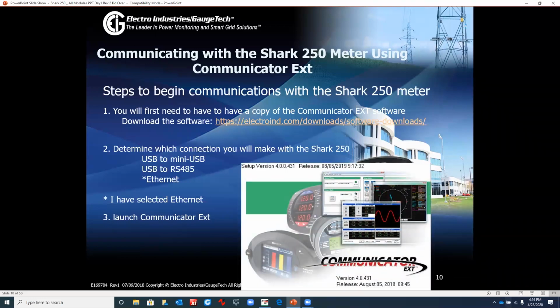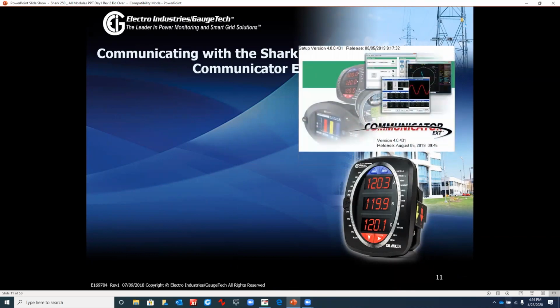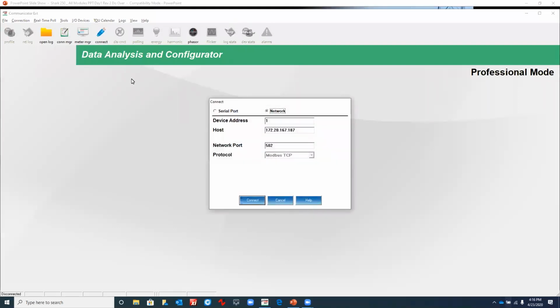So I'm going to jump out and let's take a look at what the Communicator will look like once we connect to it. We'll click on the Connect button, and we'll notice a pop-up screen that has Serial and Ethernet. In this case, we're going to choose the Ethernet, or network connection. If we chose the serial connection, we would have used one of the USB connections that we talked about before, which is USB to USB or USB to 485. Again, in this case, I prefer to use the Ethernet option and connect to the meter.